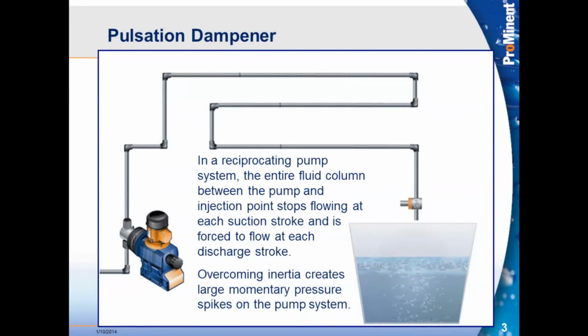Pulsation dampener. This slide is trying to show you a system, and we've all seen systems probably very similar to this. So we have a very long discharge run. It has a lot of bends in it. As the pump is on the discharge part of the stroke, we accelerate all of the fluid in that line between the discharge of the pump and the injection point.